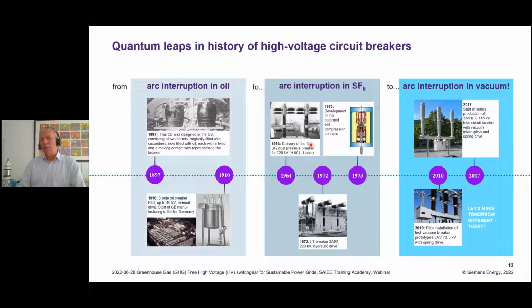Now this will be substituted by arc interruption in vacuum. You see here a few pictures. So we did the first installations in 2010 for high voltage, for 72.5 kV, and in 2017 for 145 kV.